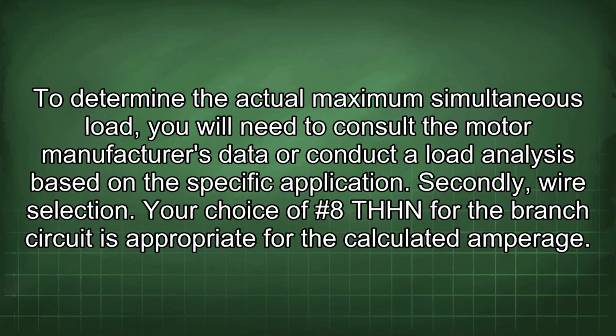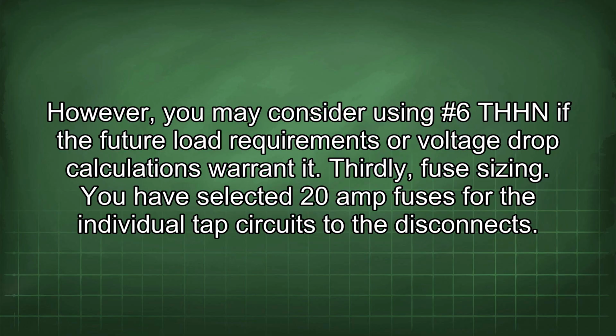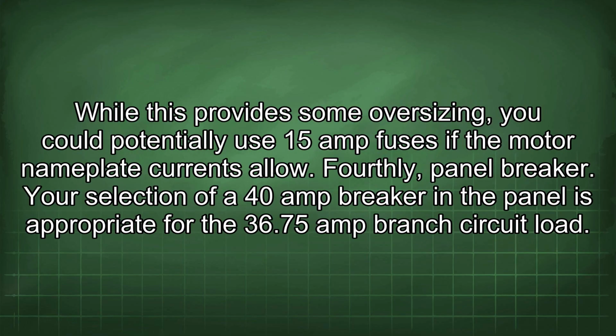Secondly, wire selection. Your choice of #8 THHN for the branch circuit is appropriate for the calculated amperage. However, you may consider using #6 THHN if the future load requirements or voltage drop calculations warrant it. Thirdly, fuse sizing. You have selected 20 amp fuses for the individual tapped circuits to the disconnects. While this provides some oversizing, you could potentially use 15 amp fuses if the motor nameplate currents allow.